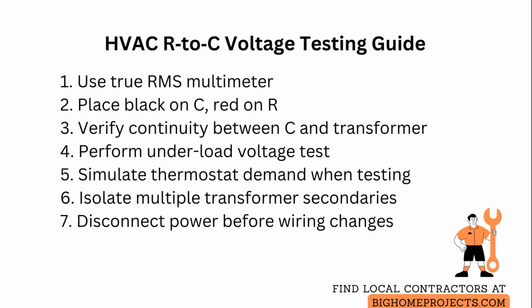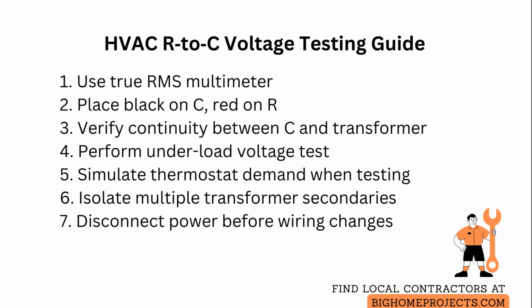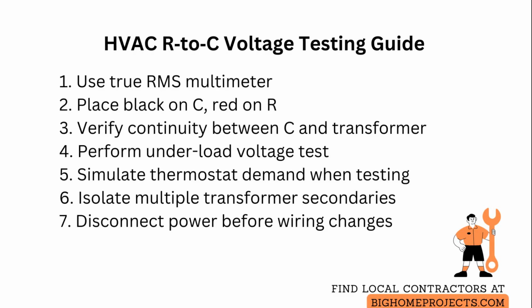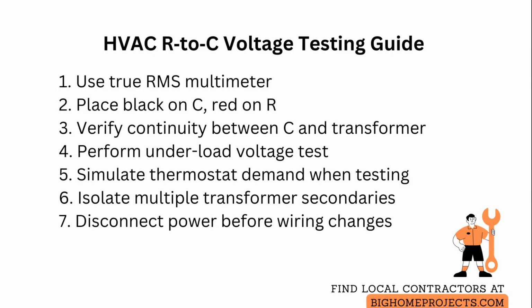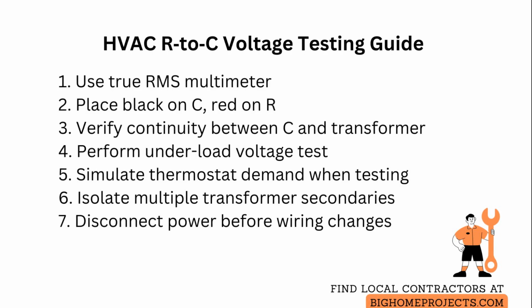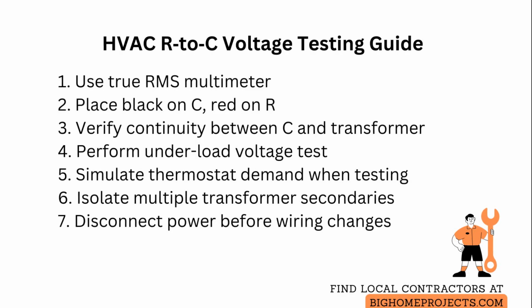When measuring, avoid using the low voltage terminals while the system is being powered by any auxiliary sources such as battery backups or electronic adapters that could skew the alternating current measurement. If the system has multiple transformers or an add-on air handler with its own transformer, isolate each secondary and label wires to prevent backfeeding and inaccurate voltage readings.